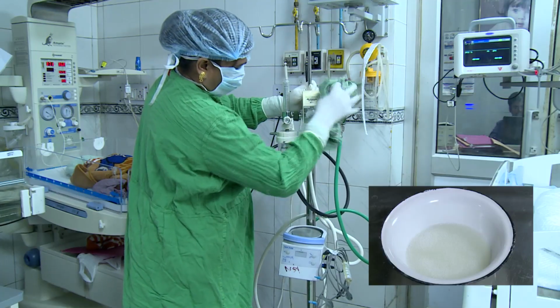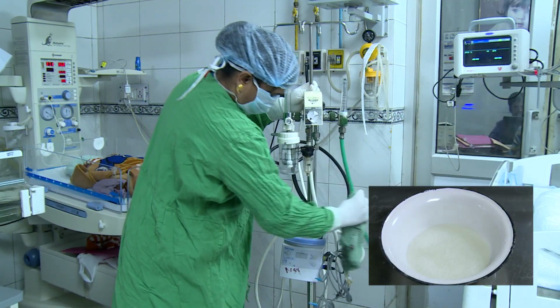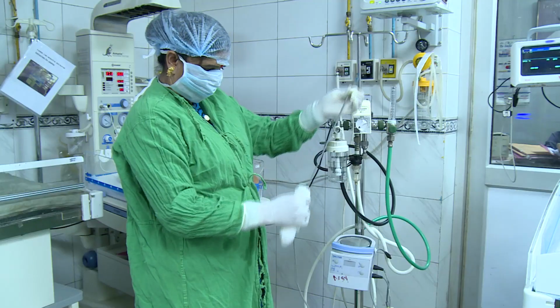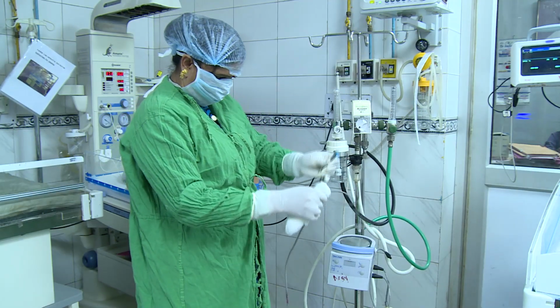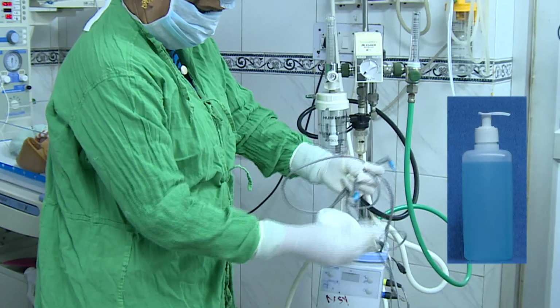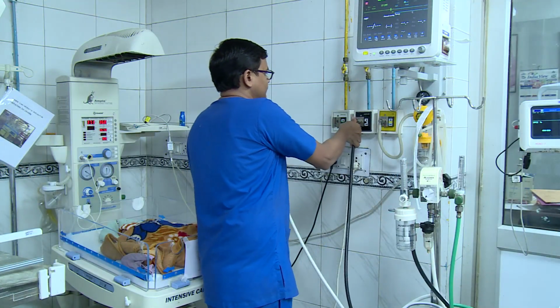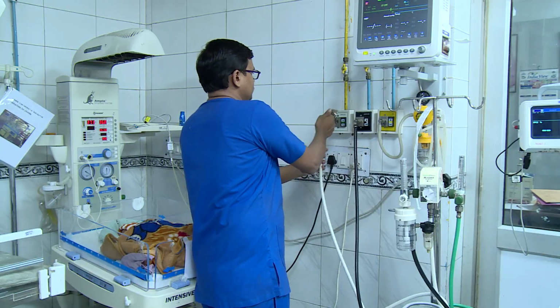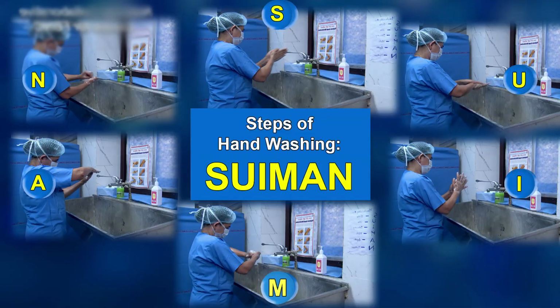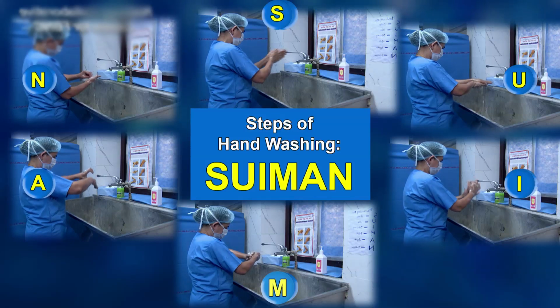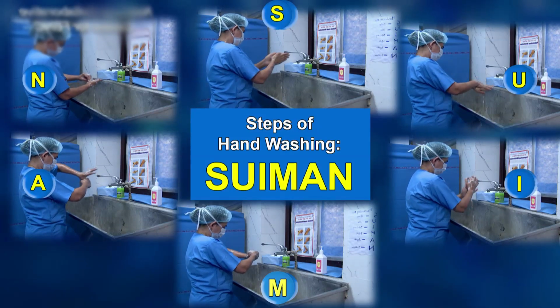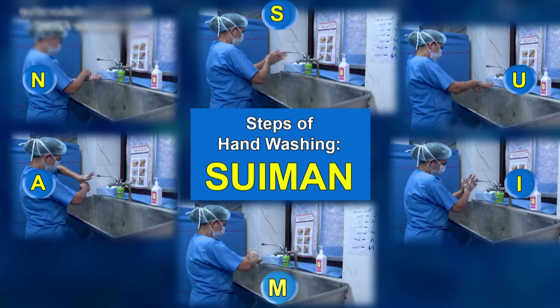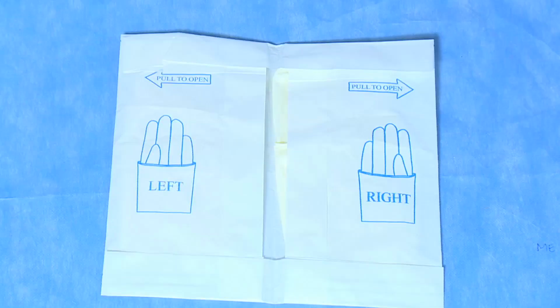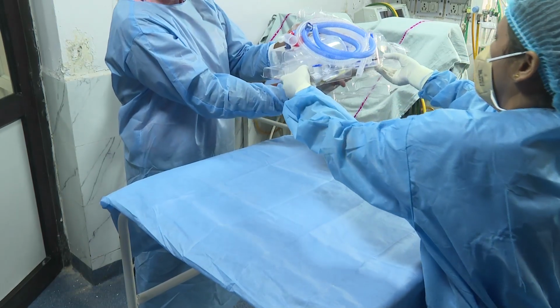Before placing a baby on CPAP, clean the CPAP machine with 2% glutaraldehyde or any other surface disinfectant. The heater wire and the temperature probe are cleaned using a soft cloth and 70% isopropyl alcohol. First, connect the CPAP machine to the air supply and the central oxygen supply. Hand washing is important before circuit attachment. Wear sterile gloves.